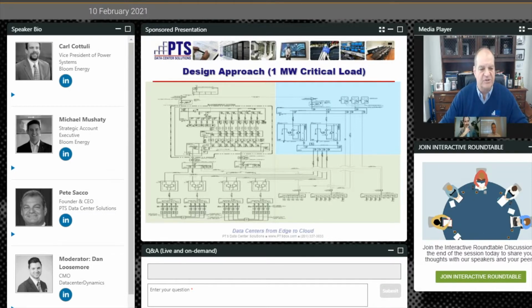Below that box, you'll see some distribution boards, four static switches, and then distribution, and that is where the 2N is happening—I'm sizing the 2N in this particular design. Each one of those UPSs is a 500 kilowatt box tied back to each of the two separate data suites. We're going to see a picture of it, I promise. And then the generators to meet that need, which I could reduce the blue to as much or as little of the 2N load as I actually want.